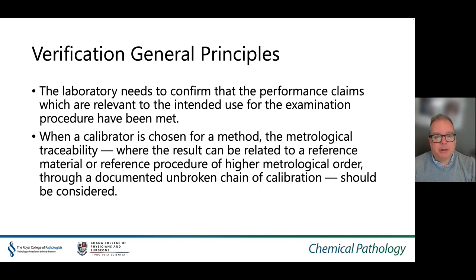The laboratory needs to confirm that the performance claims relevant to the intended use for the examination procedure have been met. When a calibrator is chosen for a method, metrological traceability — that is where the result can be related to a reference material or reference procedure of higher metrological order via a documented unbroken chain of calibration — should always be considered.